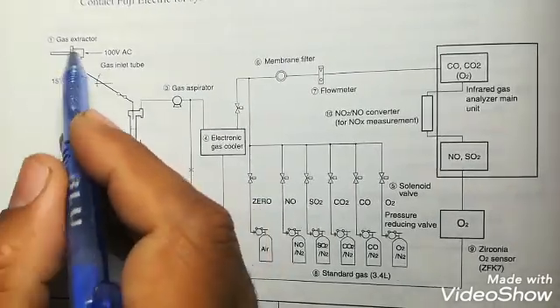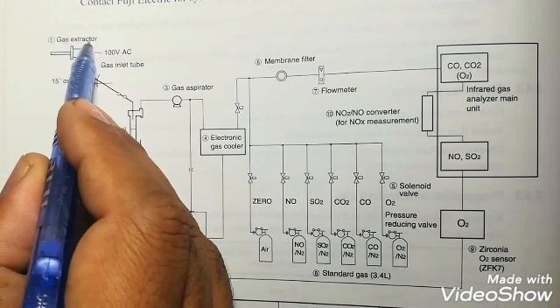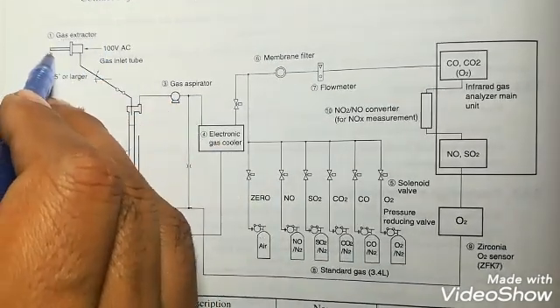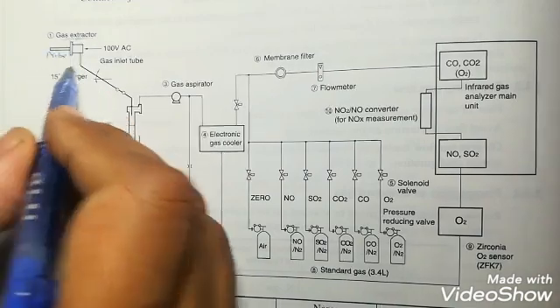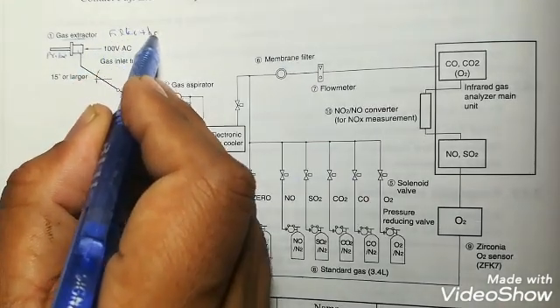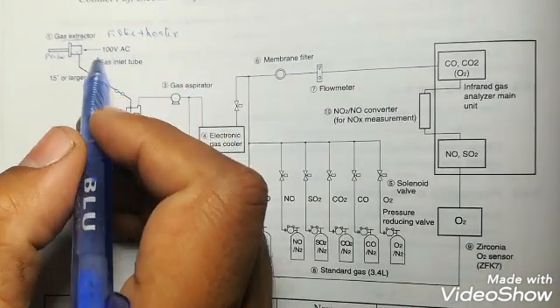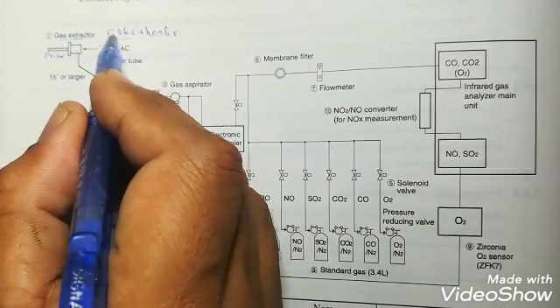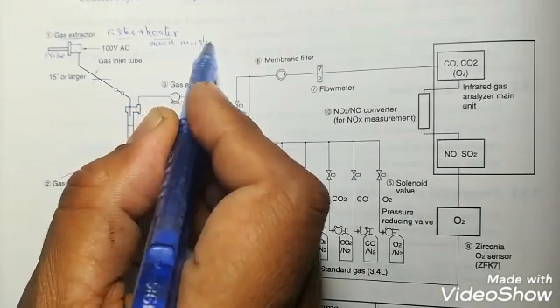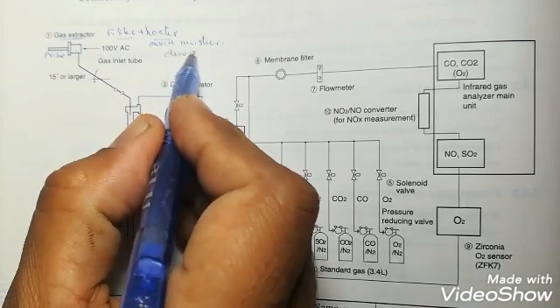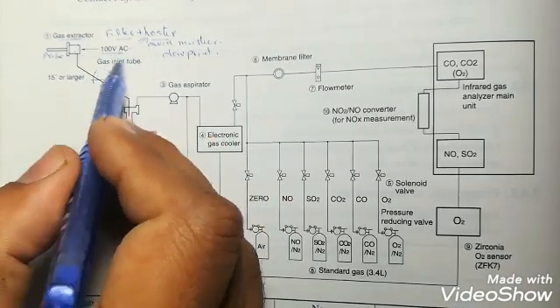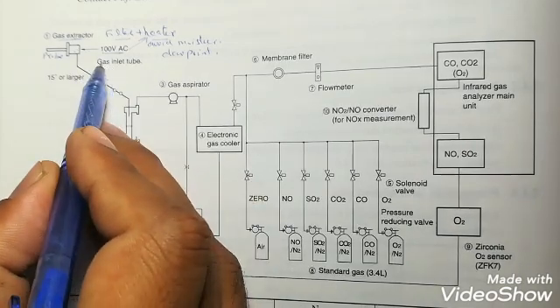Here you can see the flow diagram of a gas analyzer. This is the gas extractor. The gas extractor has a filter which is stainless steel filter and a heater. This filter filters out the particles and dust particles inside the sample, and this heater heats the temperature of the sample so it doesn't reach the dew point.